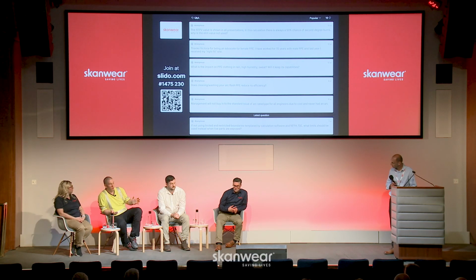So I come up with an approximation, never as good as a full system study, and they're not always right either because of the scenario bases within the studies. But there's also calculators, apps on our phone, or we go old school and use the basic calculations, as shared yesterday, which will get you the same answers. The apps are great, transformer impedance is usually there, and transformer sizes aren't always difficult to find, if there's an SLD it'll be on there, or go for a little walk and look at the equipment, at the data plate. Within half an hour, the time it takes to get the gear out of the van, we're doing a point-of-work risk assessment and collecting the data. It gives us time to stop and think about what's going on, what's wrong, why we're here, why they called us out at 11 o'clock at night. We can easily put together a safe system of work within the room, for that specific task, very quickly, and we've all got our gear with us anyway.